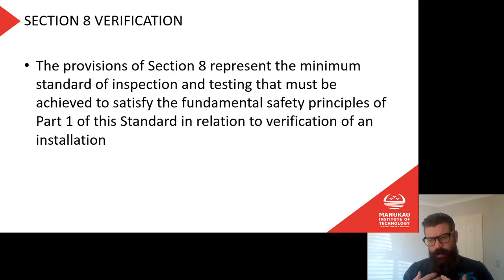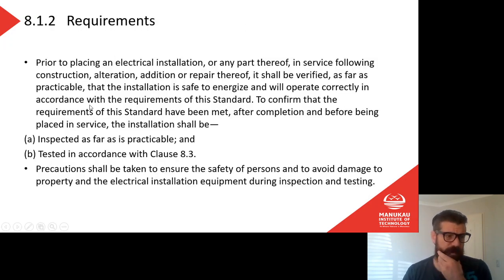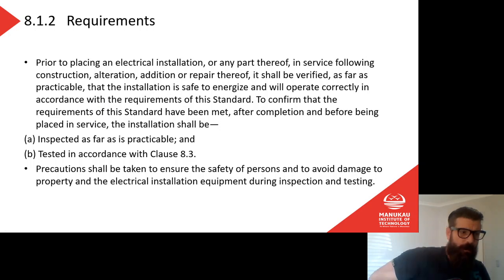Why is that important? Because I think I've said it before, you can do all sorts of shady stuff, but as long as you test properly, you know that things are going to be safe. I'm not saying do shady stuff. What I'm saying is when we test and inspect, if we do our testing and inspecting properly, it'll tell us whether we've done something shady, because if we pass all the tests, then we know that things must be safe. So we're going to delve into section 8 a little bit more, because as I said, it's the most important one, at least for us now.